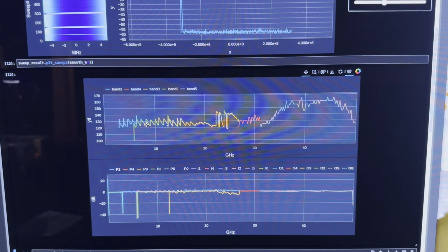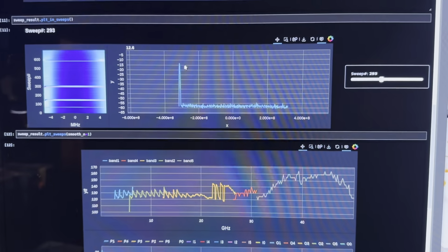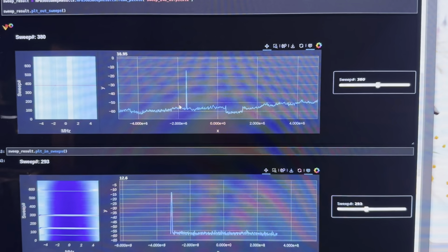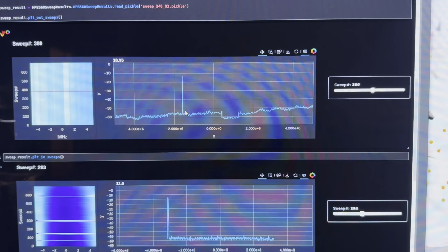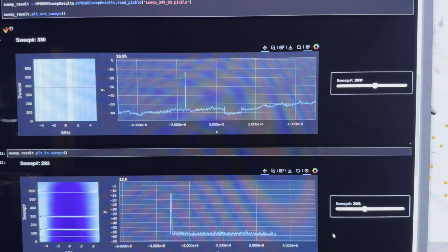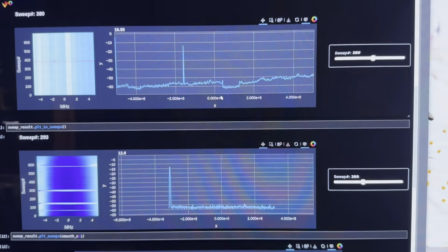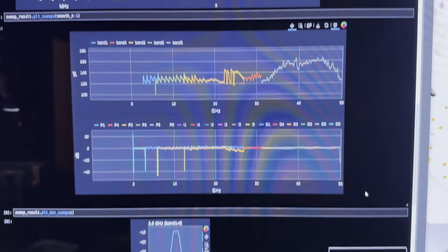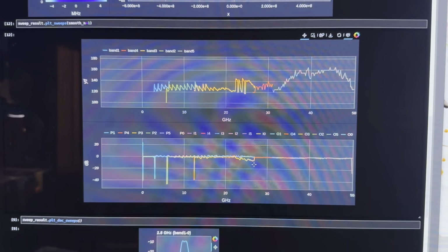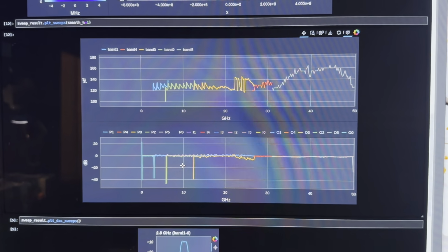And in fact, if you were to take this and program it into the instrument, you would get really awkward results, like you would get zoomed out peaks doubling up as the fine adjustment in the preselector went past one of those sawtooths and would bump over that YTF peak, and then you would get this slipping into the image frequency, and it's just a mess. So you don't want that. You want to smooth the YTF and be consistent, not hop between different optima on adjacent frequencies.